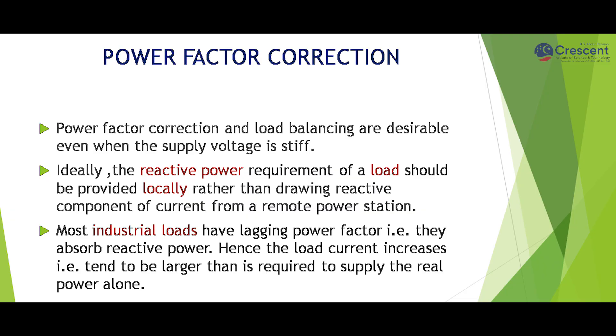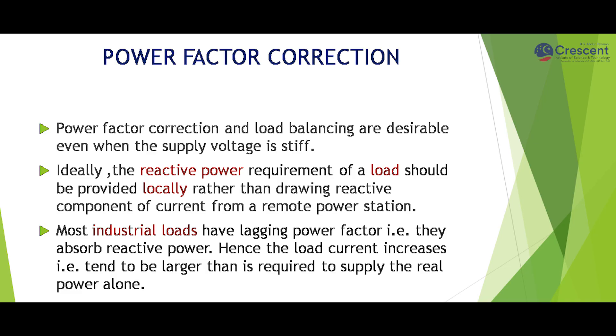When there is no voltage regulation required, the reactive power requirement of a load should ideally be provided locally rather than drawing the reactive component of current from a remote power station. Most industrial loads have a lagging power factor, meaning they absorb reactive power, and hence the load current increases.